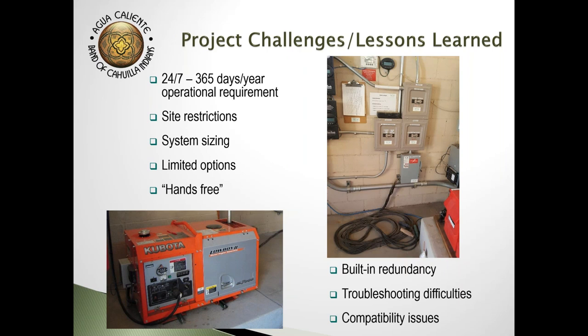We incorporated built-in redundancy, so the system could run off the batteries with the solar, or run the generator. In the upper left, we had a switch so we could isolate components of the system—for instance, if the generator wasn't working, we could isolate it while we work on it, or disconnect the solar and batteries and run on the backup generator. If everything fails, which is what we were relying on before, there's a power cord at the bottom where we could run a cord out and hook up to the diesel generator. So no matter what, we could always have power to the building.